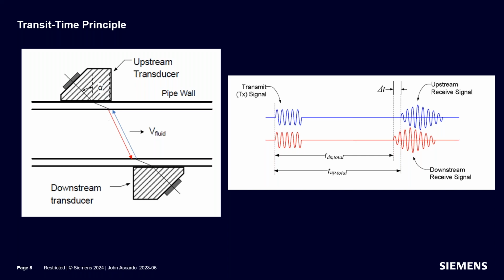But in any case, you have a transit time downstream and a transit time upstream, and that difference in time is due to the flow rate. Now, this is the fundamental way that all clamp-on transit time flow meters work, regardless of who makes them, but how you accomplish it is what sets things apart. The method for accomplishing this measurement varies somewhat from manufacturer to manufacturer, and there are a number of factors that influence what occurs in the process. So we're going to take a look at how Siemens handles those changes and what we've done over the years to pioneer some of these measurement techniques and what sets us apart from the competitors.